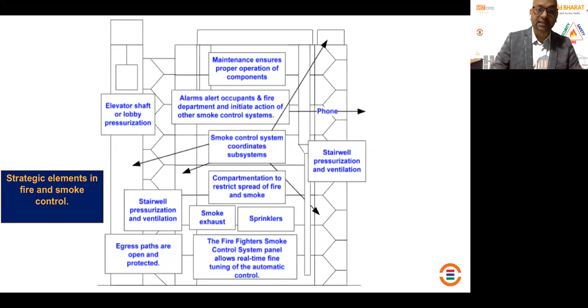Then let us look at the components in further detail. When you are looking at this as a part of the communication system, or a system complementing your smoke extraction systems, what are the ingredients, what are the components involved? First, the stairwell pressure systems. Essentially, what we are looking at is extraction fans. Where are we going to place that extraction fan? What RPM, what CFM am I going to have for the extraction fan? What calculation have I done for right sizing? That's very important.